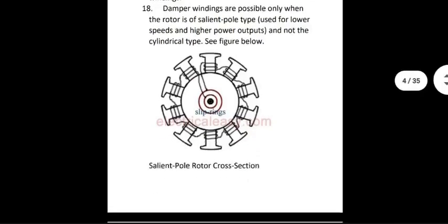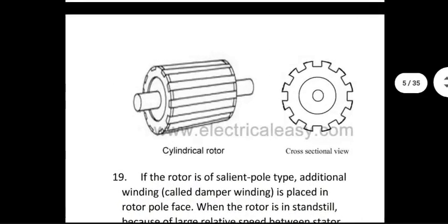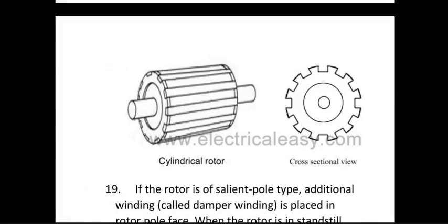Okay, so the rotor, as I said, could have poles which are either physically present or electromagnetically simulated. For low speed, the physical poles are okay, and that construction is known as salient poles, SALIENT, salient poles. For high speed, the poles start coming off, and it's not a good scene for sure. So instead of having mechanical poles, we have electromagnetically simulated poles on the rotor also. Then the rotor is known as cylindrical rotor.